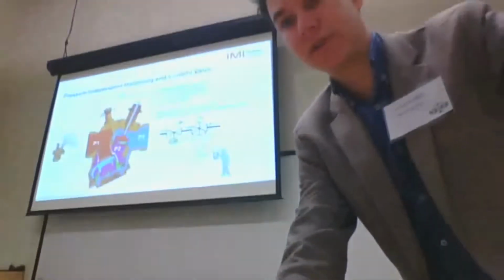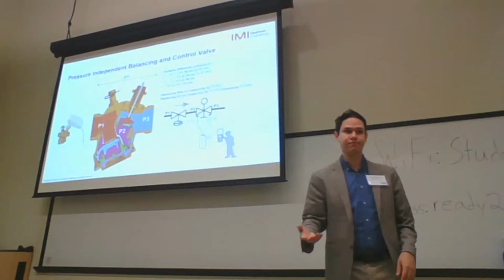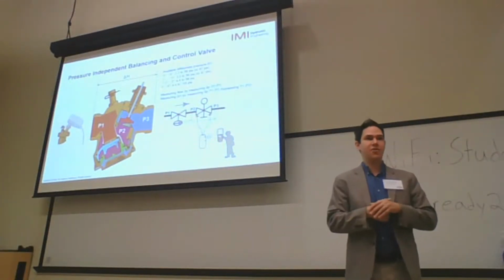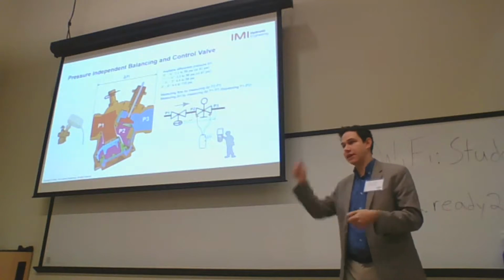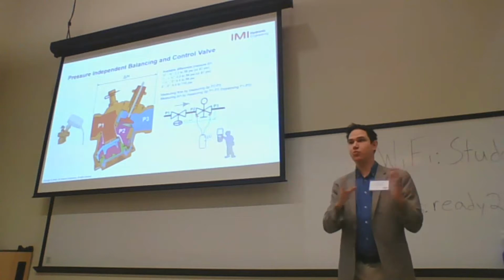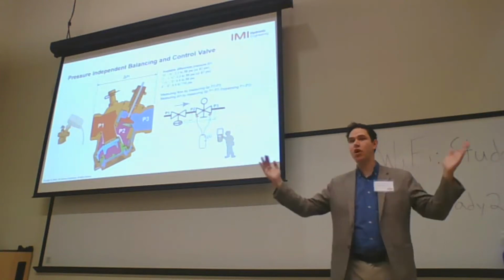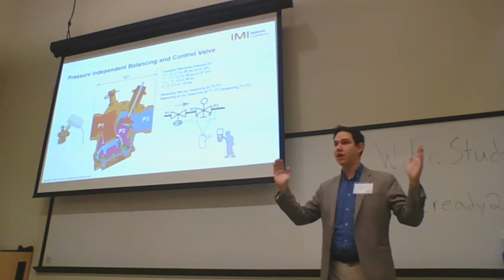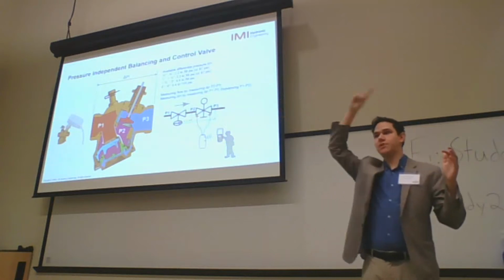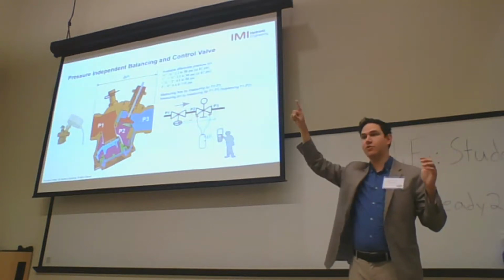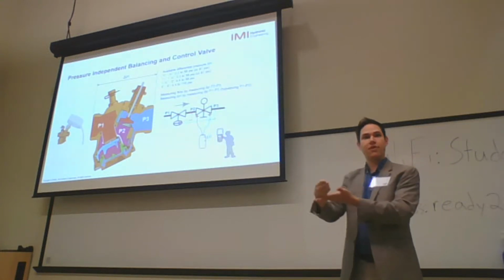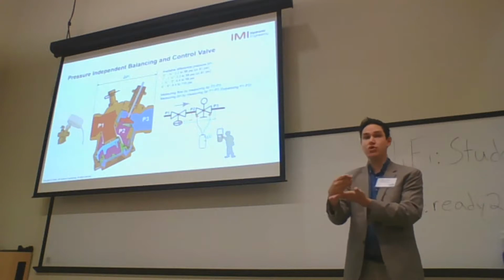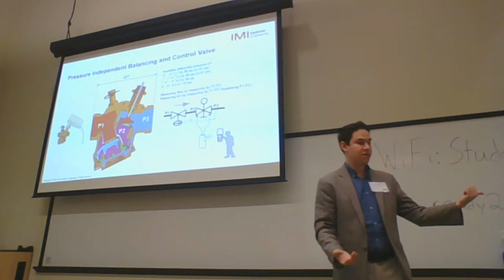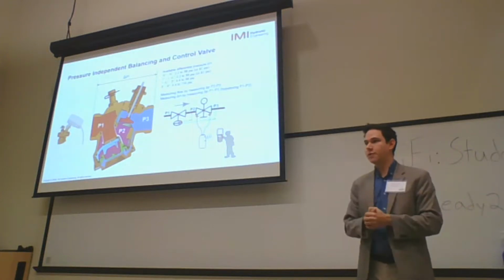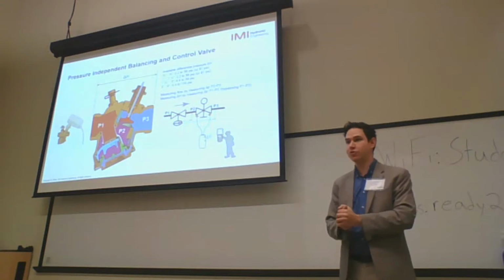So you can also find the problems of the installation. I can share one thing that happened to me in one of the installations where I was taking some measurements. It was a data center. In a data center, you have many butterfly valves, many shut-off valves for redundancy, many things like that. In one case, I measured a huge differential pressure difference between two units. They were fairly close, and it didn't make sense. The point is, I couldn't see the pipes because they were right above the ceiling. So I asked the mechanical contractor to take a look, and he found the butterfly valve at 45 degrees, just causing a huge pressure drop. The way I was able to find that was by measuring the available pressure on the two units and thinking that it was too huge a number to be true.